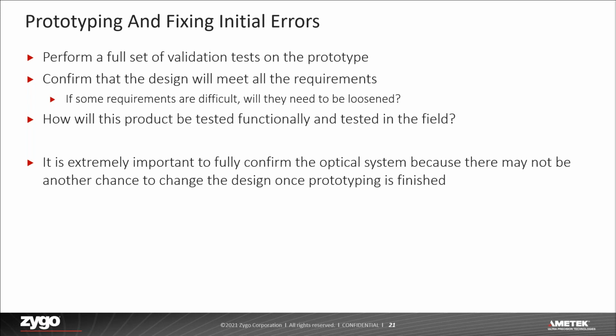If you are working with an optical system that's small, an endoscope for example, you may not realize how difficult it will be to assemble and test your device. In the case where a device needs to be sealed, you need to make sure there is the possibility for potential rework if the manufacturing or alignment isn't meeting the requirements. This rework might be for the initial build or for servicing later in the field. Remember, most medical optics are fixed at the end of the design phase. If you're able to have a prototype run and see what worked and what didn't, you may be able to adjust your design accordingly. You may not get another chance to fix errors in the device design.